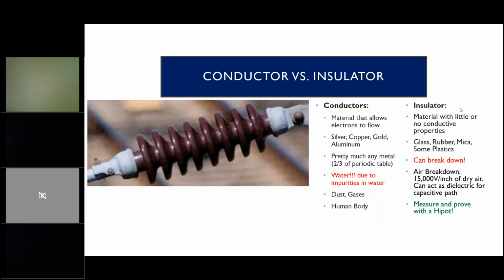Now, insulators are the opposite. They have little or no conductive properties, examples being glass, rubber, mica, and some plastics. But even an insulator can break down. So an insulator that works at 1,000 volts might not work at 3,000 volts, as an example. And that's why we use HIPOTs to measure these things.